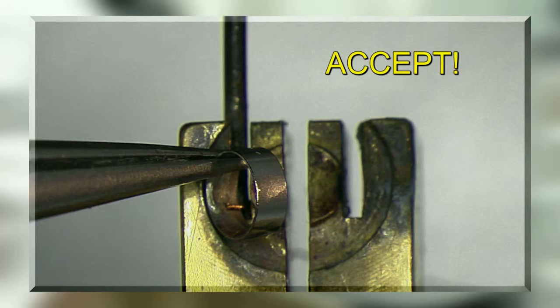This is what we are looking for. The brazing paste should have a smooth, shiny appearance, showing it was completely melted, but not overheated.